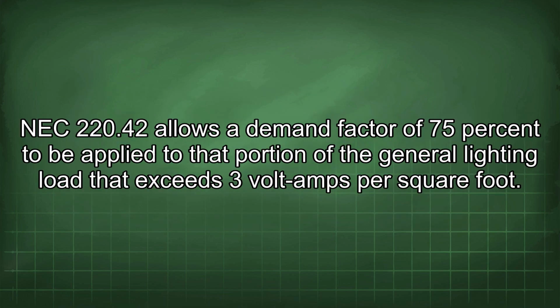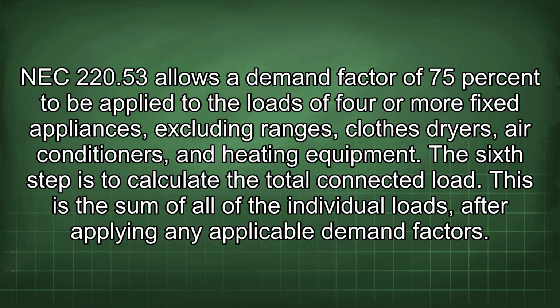NEC 220.42 allows a demand factor of 75% to be applied to that portion of the general lighting load that exceeds 3 volt amps per square foot. NEC 220.53 allows a demand factor of 75% to be applied to the loads of 4 or more fixed appliances, excluding ranges, clothes dryers, air conditioners, and heating equipment.